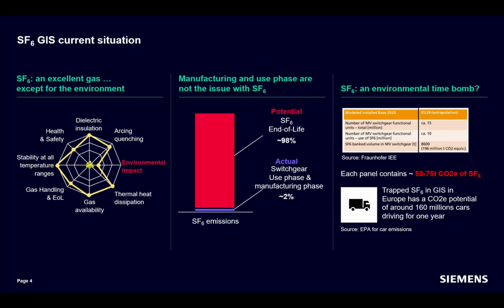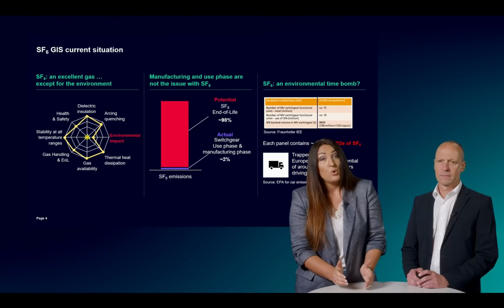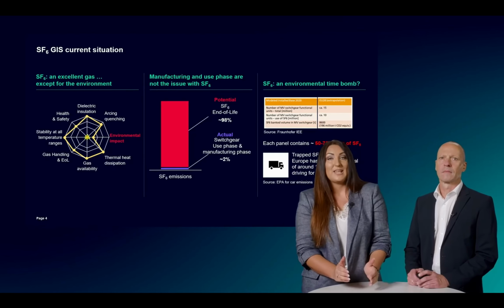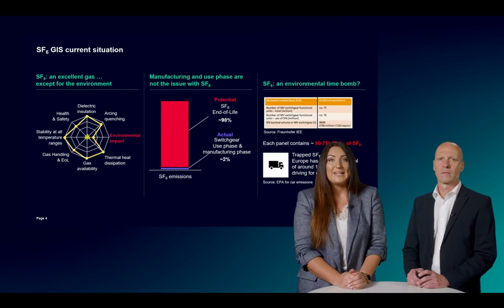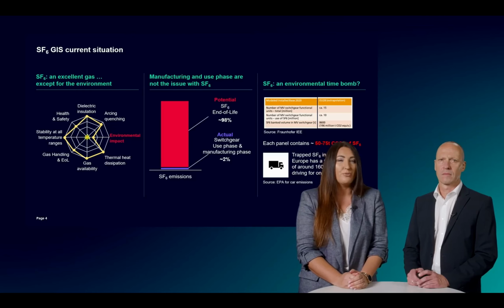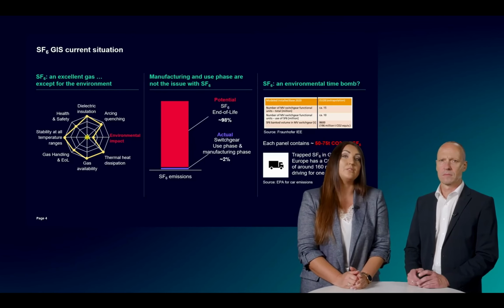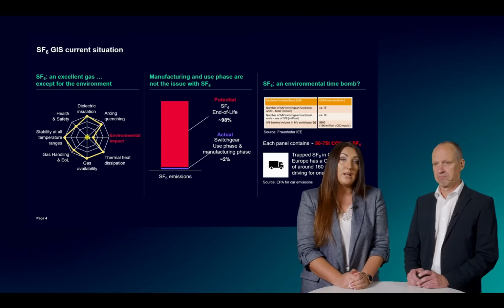The gas is also non-toxic, non-flammable, and does not have any carcinogenic, mutagenic, or reprotoxic characteristics. And it insulates 2.5 times better than air at given pressure, which of course enables a very compact design of the switchgear. However, SF6 is the most potent greenhouse gas known if released into the atmosphere, with a lifetime of around 3,200 years, which is extremely long-lasting.